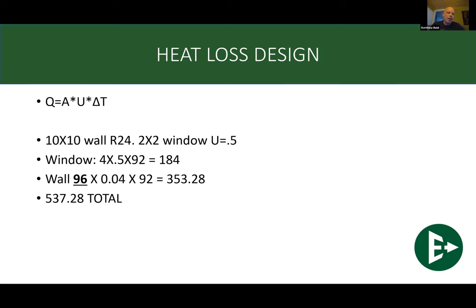And then your wall, which is now 96 square feet because we take out the window, times 0.04, which is 1 divided by the R value of the wall, 24, times that again by the temperature differential, 352. So for that exterior wall with that one 2 by 2 window in it, we get 537 BTUs required for that one exterior wall. When we're doing a heat loss for a home, and this is just for quick overviews, we're only concerned with exterior walls. If it's an interior wall, we're not super concerned with that in the design.